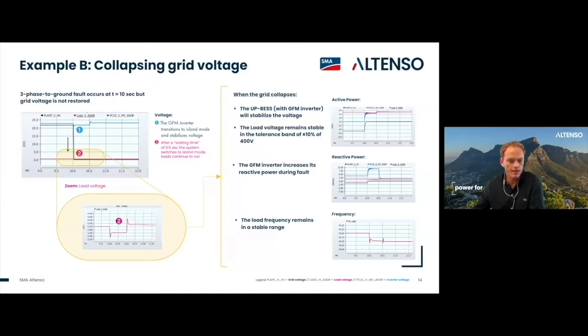And if you look in the yellow block here, the image shows that the islanding is seamless. And by seamless, I mean that the system holds the voltage and frequency of the load within stable ranges. So when the grid voltage does return, the system will then automatically switch back from island mode and synchronize back to the grid seamlessly.